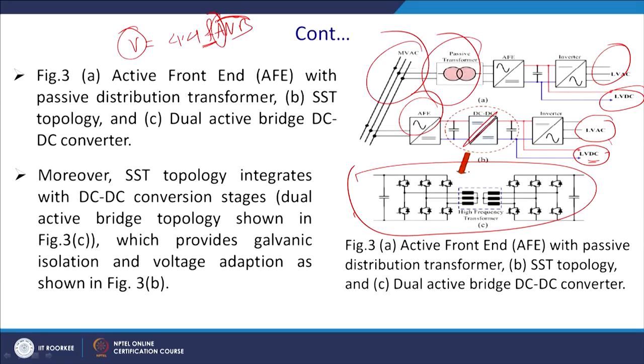The overall SST-based microgrid will be more compact because of high switching frequency, and with the penetration of wide-bandgap devices like silicon carbide, the power handling capability can reach megawatt levels with better functionality at the AC grid interface. In conclusion, the key challenge lies in designing the high-frequency transformer — one must be a very good magnetics designer. The transformer turns ratio remains essentially the same, but the physical size is 200 times smaller, giving a much more compact system. Thank you.